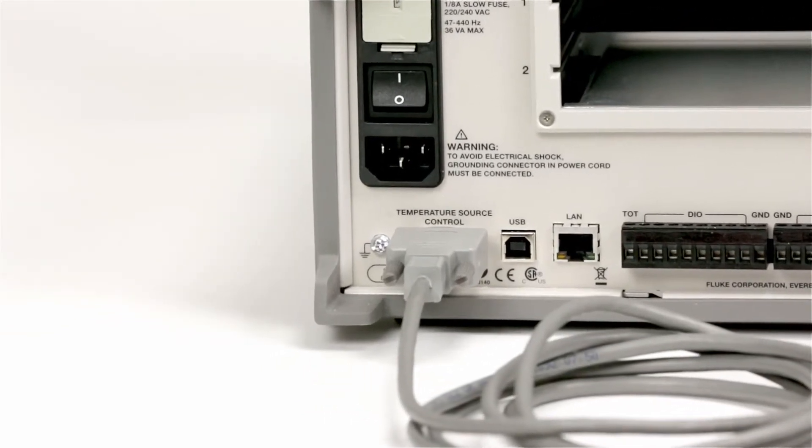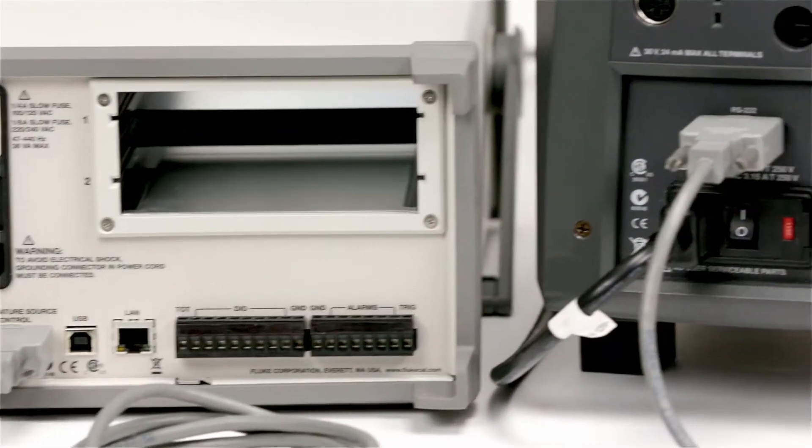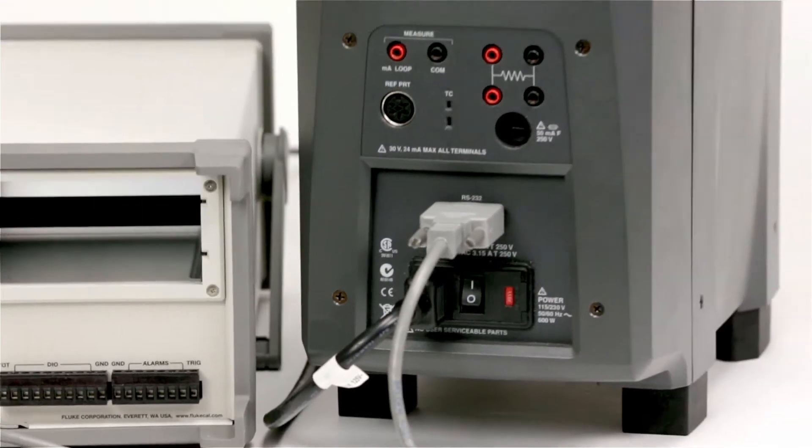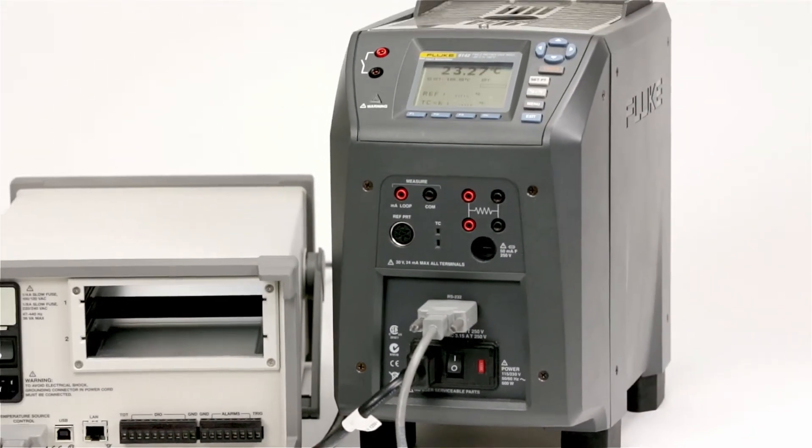The automated test feature is set up by first connecting the temperature source control port on the rear panel of the 1586 to the RS-232 port of the dry well.